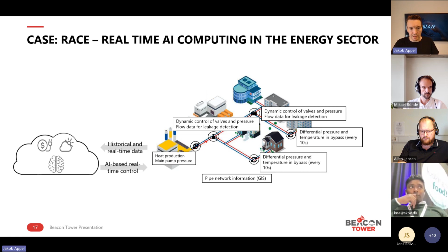...in order to make an AI-based real-time control of the current heat production, controlling the pump pressures, and also dynamically controlling the valves and pressures inside the pipes, based on this AI model that has developed an algorithm from historical data, but now also takes into account real-time data to control the different real-time actuators.